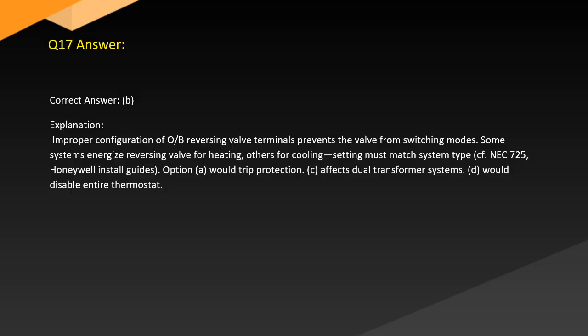Answer. Correct answer: B. Explanation. Improper configuration of reversing valve terminals prevents the valve from switching modes. Some systems energize the reversing valve for heating, others for cooling. Setting must match system type. CF. NEC 725, Honeywell install guides. Option A would trip protection. C. Affects dual transformer systems. D. Would disable the entire thermostat.